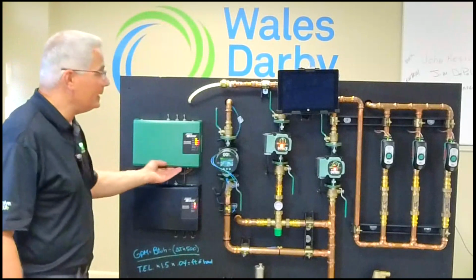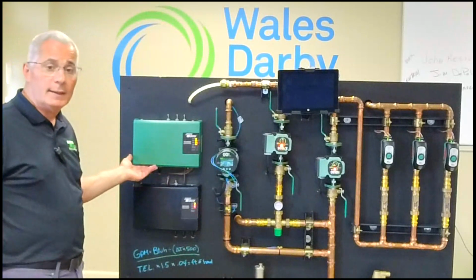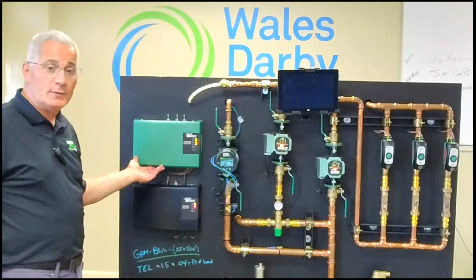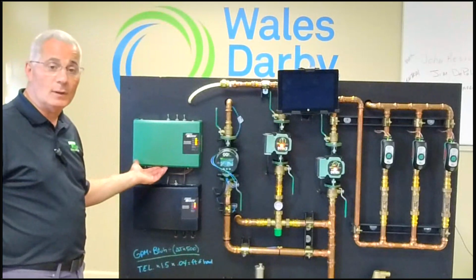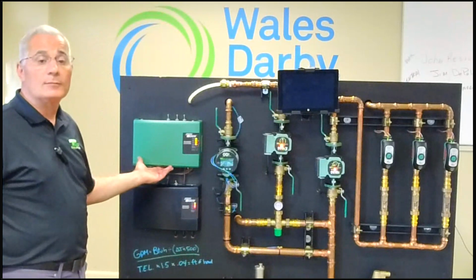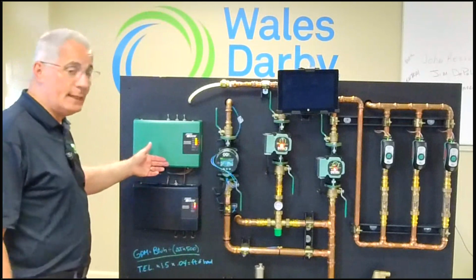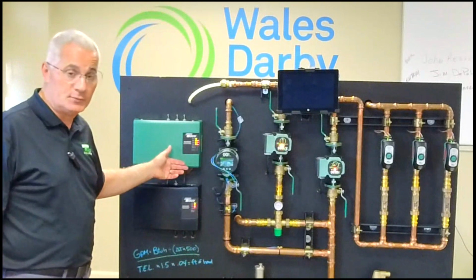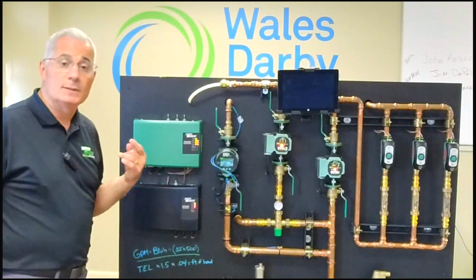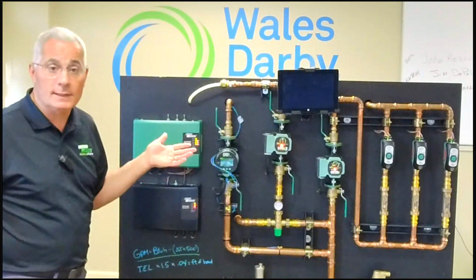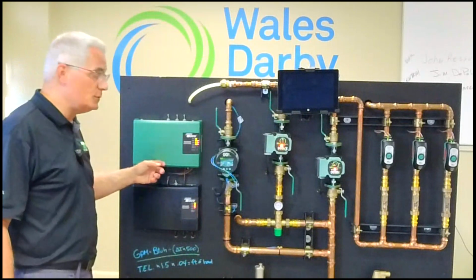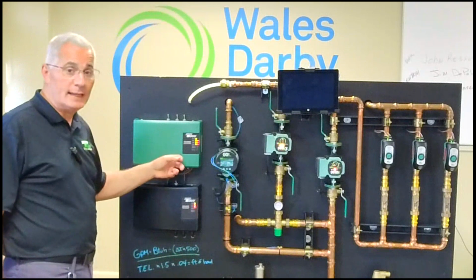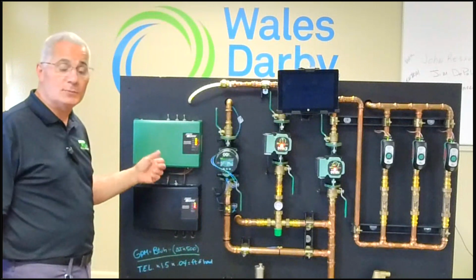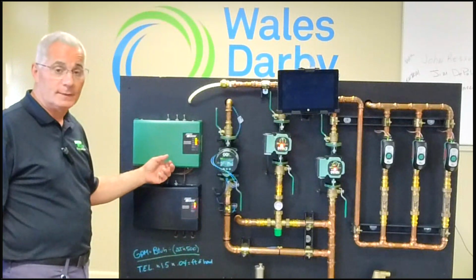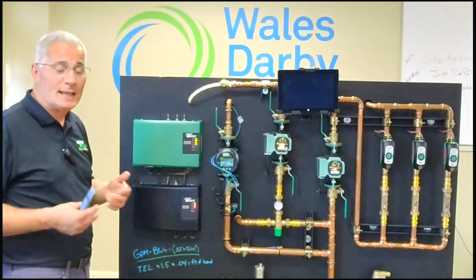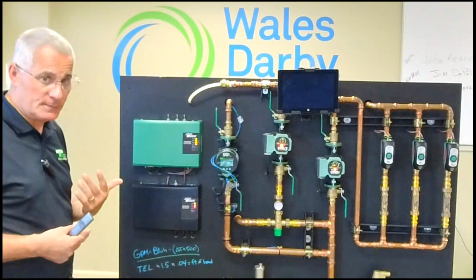Anyway, on the bottom here is where I can put my zone valves. So whether I have 2-wire, 3-wire, 3-terminal, or 4-wire zone valves, we label 24 volts, we label end switch. So if it was your typical Honeywell, your 2 yellows are going to go to the 1-2 terminal. Each zone will have this. And then the 2 reds would go to the 3-4 terminal. So no wire nuts. So that bird's nest disappears.